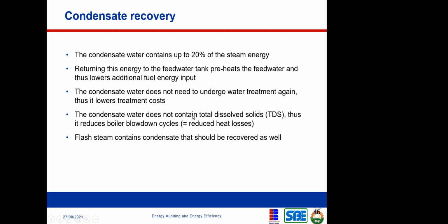The condensate water does not contain total dissolved solid. Thus, it reduces boiler's blowdown cycle. Okay. Remember, anytime you're introducing new water, fresh water into your boiler, the chances that you're also introducing total dissolved solid that can also impact your boiler, but your condensate that you're returning to the boiler does not contain TDS. So it's an added advantage for the boiler. Then flash steam contains condensate that should be recycled as well. I've talked about flash steam, where you have holes maybe around your steam distribution lines, and you have this steam that are leaking and all of that.